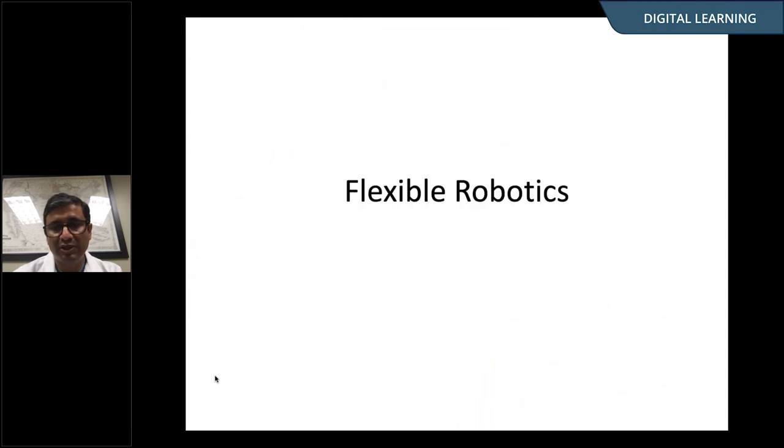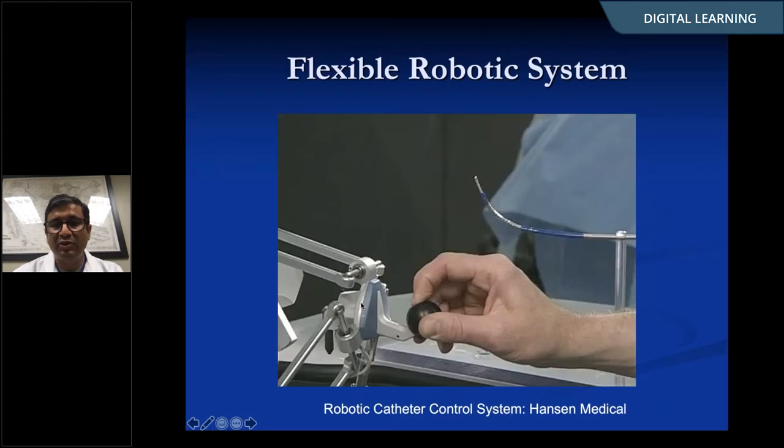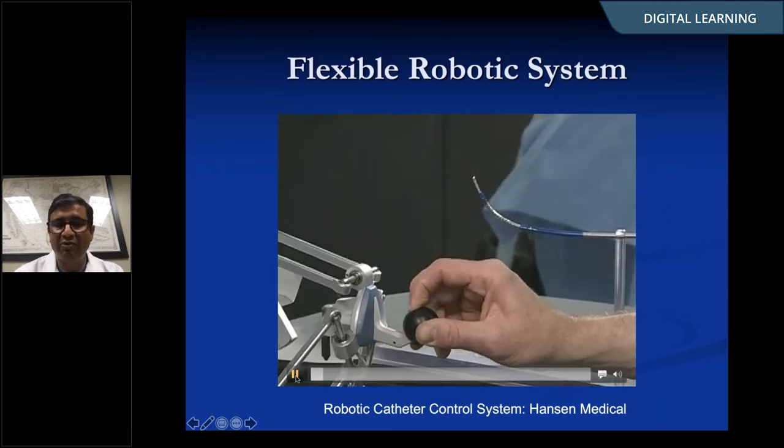Moving on, everybody is familiar with the manual endoscope across all surgical specialties — this happens to be a ureteroscope, but you could substitute a gastroscope or bronchoscope. It has an external lever for articulation, a long shaft of variable diameter, and usually a single working channel. All the movements except deflection in one plane are transmitted by the surgeon from the outside across the small tube to the inside. If you were to give this to an engineer, they would say this is the most inefficient way of controlling the tip of a flexible catheter.